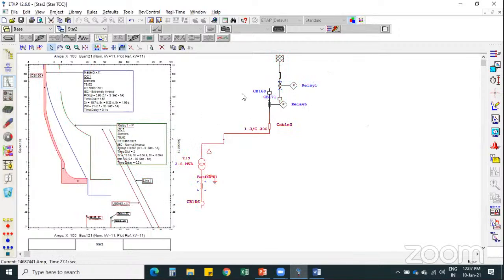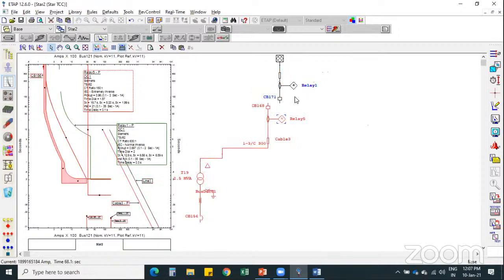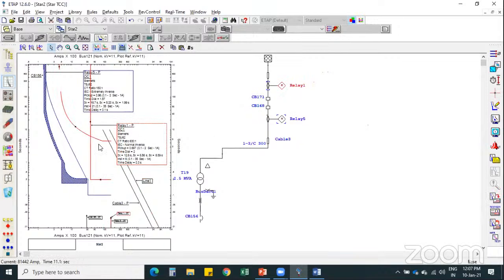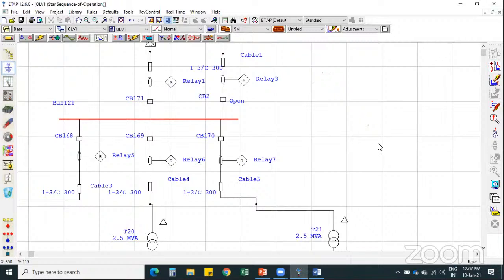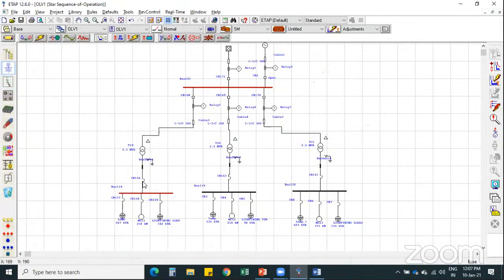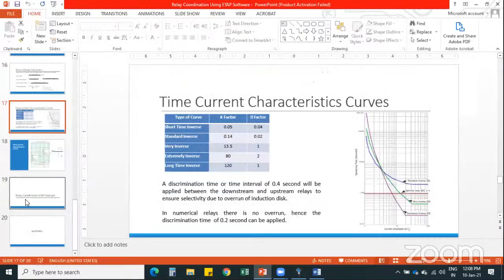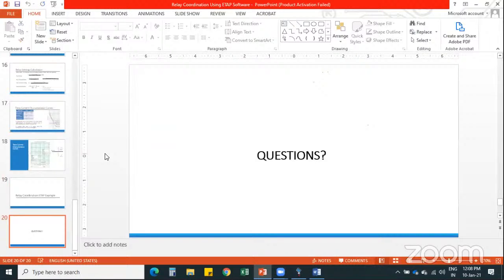Okay, wait. So this is for the incomer relay. Okay. And this is the fault current for this relay. Relay number 5, that is the transformer primary side. So this is the relay coordination, what actually the thing is, and how we can cross-check with the time current characteristics curve. That is all from here with ETAP. And any questions from our audience, we can hear.